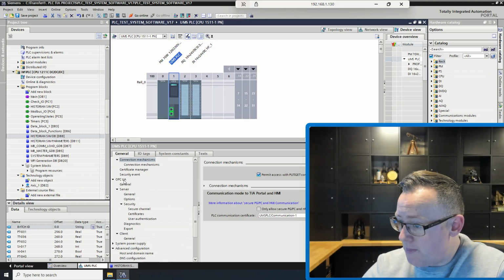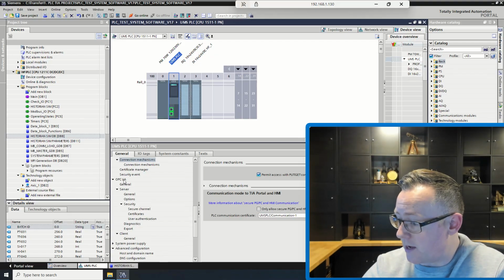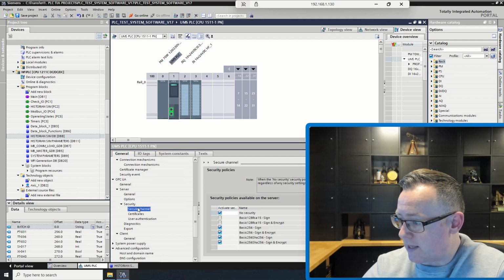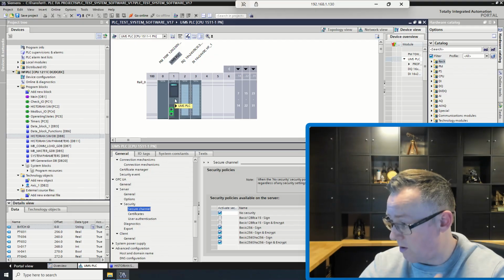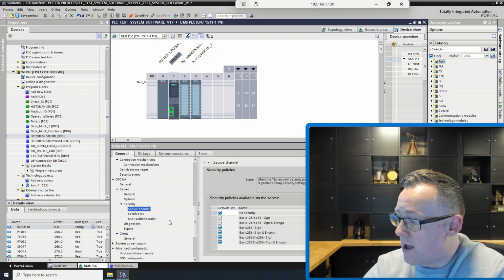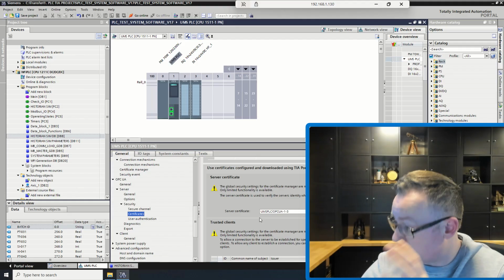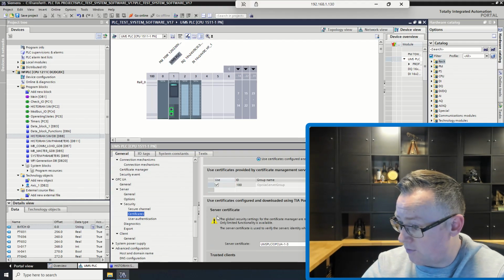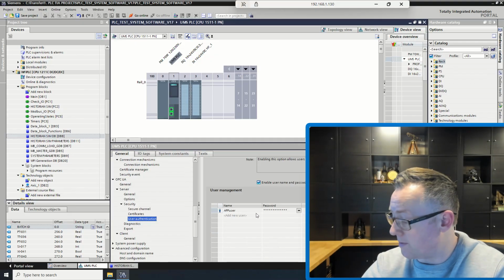So in terms of the OPC server itself, getting it working with Kepware can be a little bit tricky. The core thing is that you have the actual authentication method set inside the PLC. Here I'm just looking at the hardware settings for the controller, that you actually have a genuine certificate. That's a key thing. So you have a certificate, you have authentication, and then you have an actual user set up in the PLC.